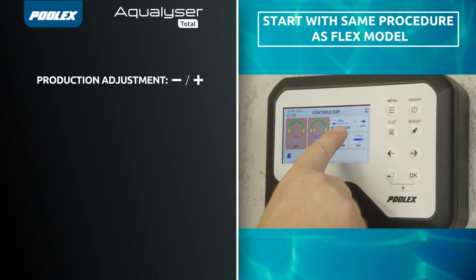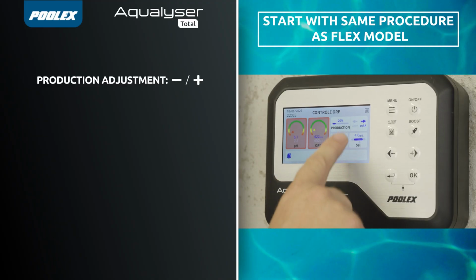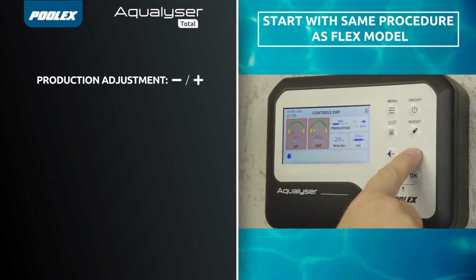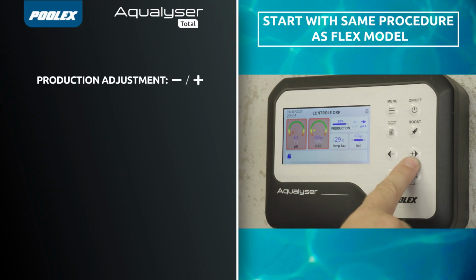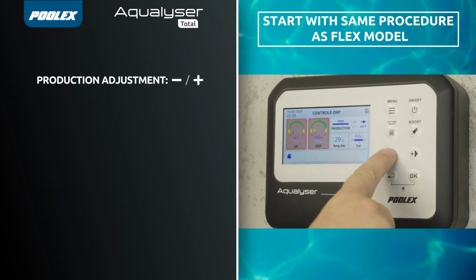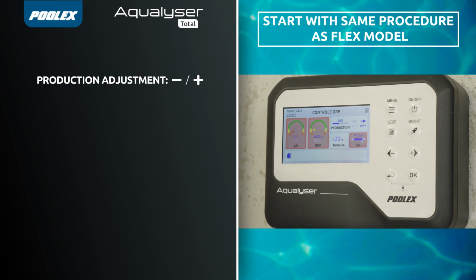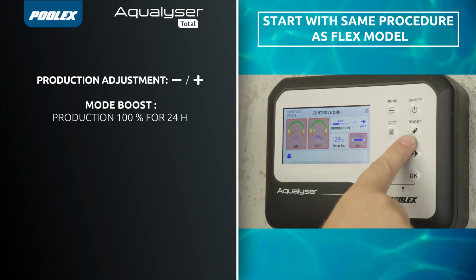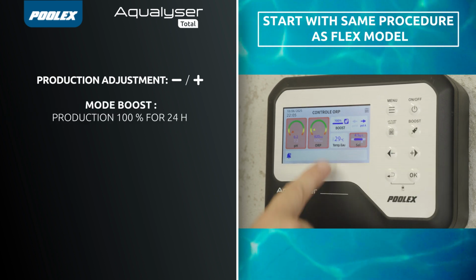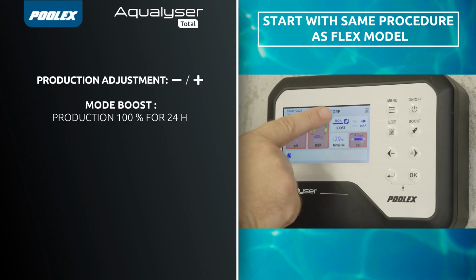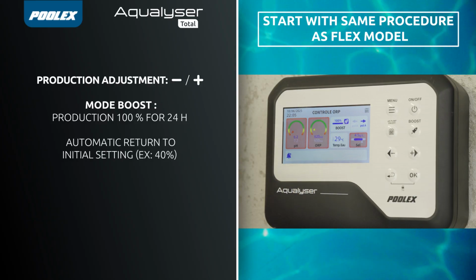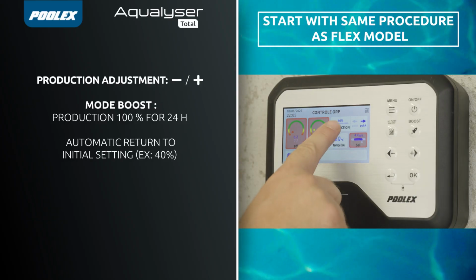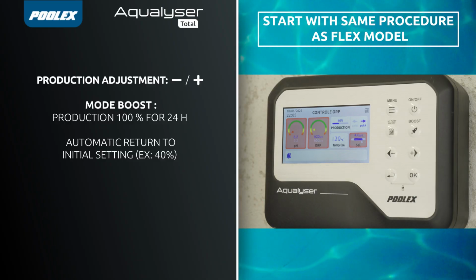To adjust ORP production, simply press the plus or minus buttons. This production depends on prior chlorine tests carried out in the pool. In case of high temperatures or increased pool use, you can activate the boost mode. The cell will then run at 100% for 24 hours, like a shock treatment. Once the boost mode is finished, production automatically returns to the initial setting, here 40%.